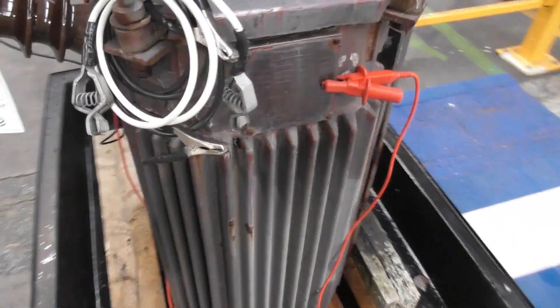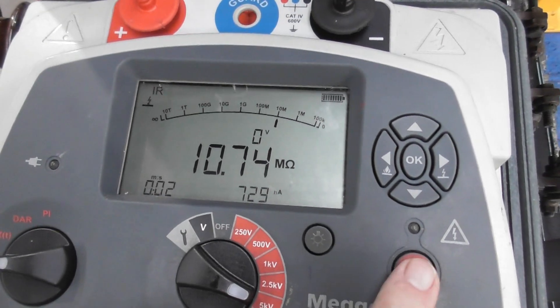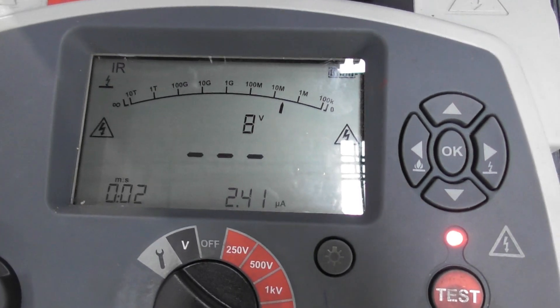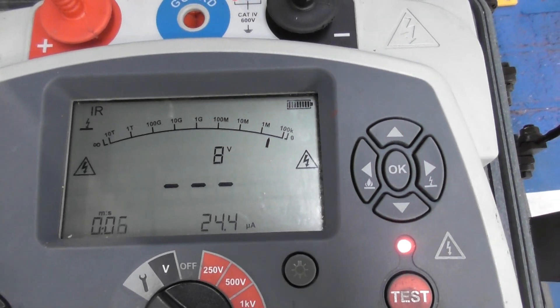Insulation test. Doesn't look good. Just did a PI already. Supposed to hold 5kV on the HV winding. It only sits at 8 volts. That's not good.